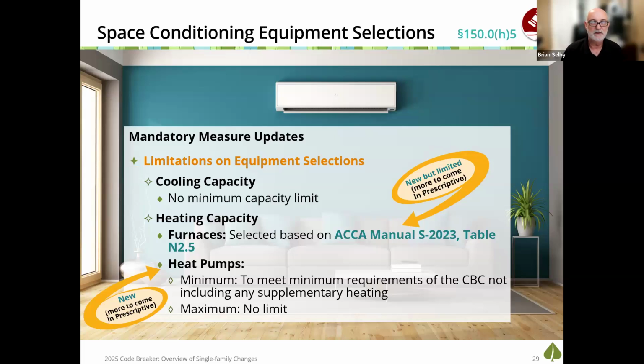Now, in addition to the load calculation requirement language that was added to the 2025 code, there's a new space conditioning equipment selection requirement that specifically applies to the heating capacity. For furnaces, selection of that system needs to be based on the ACCA Manual S. That's their system sizing calculation. In order to get to a Manual S, you have to do a Manual J, that's our load calculations. You have to do a Manual D, which is a duct design, assuming this is a ducted system. And then you get to system selection, which is the Manual S.